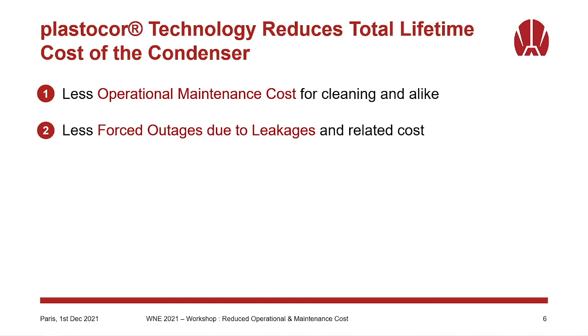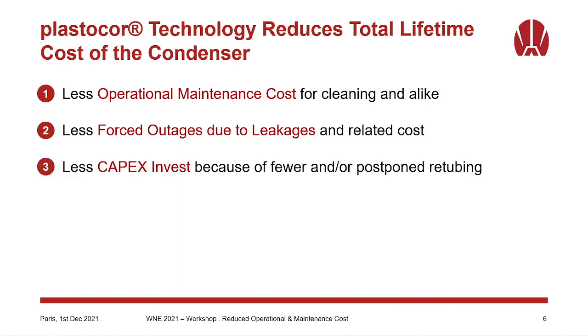Because the coating helps protect the installation, mainly in the tubes area, we can avoid some leakage. That helps save money for the outage, and there's less CapEx investment because of avoided or postponed retubing. If you have a coating on the condenser, you can avoid the coming retubing.